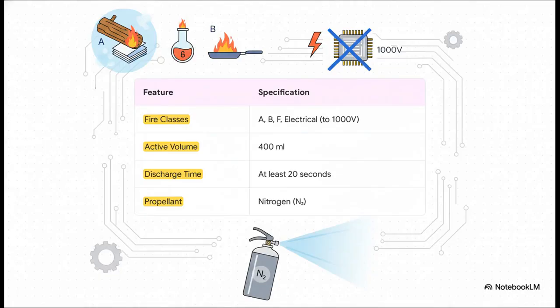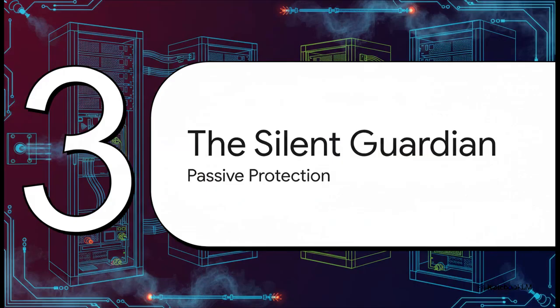From a technical standpoint, this thing is an absolute powerhouse. It can handle Class A fires, that's your normal stuff like wood and paper, Class B for flammable liquids, and even those nasty Class F fires from cooking oils and fats. It's also totally safe to use on electrical gear up to 1,000 volts. So in one little can, you've got a universal tool for basically any fire you'd run into in a public or commercial building. Okay, but what about the fires that start when nobody's around?